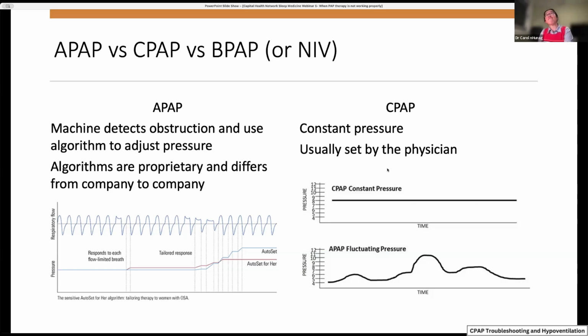Now, it's probably about 15 years ago or so, the companies started making something called the APAP, which stands for automatic positive airway pressure devices. These devices have a computer chip in them, which detects the level of obstruction and uses a computer-generated algorithm to adjust the pressure of the device. The thing to remember is that these algorithms are proprietary and they differ from company to company. So if a patient buys a ResMed machine, but the machine is broken and they swap onto a Fisher and Paykel machine, for example, although the pressure settings may be the same on APAP, the way the machine responds can be quite different. So this is an example on the left here of how the APAP machine will respond.